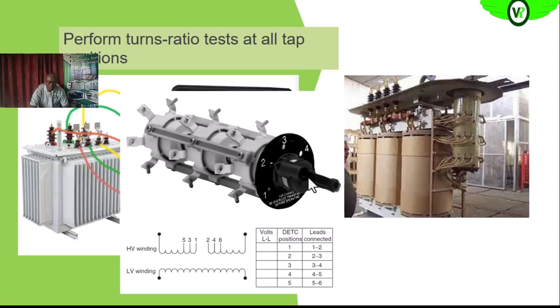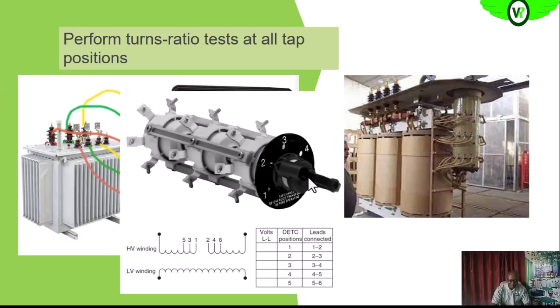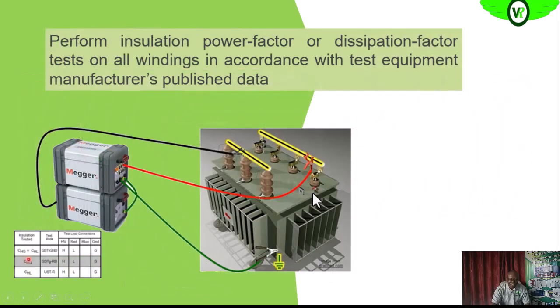So we'll do it on all tap points, or positions of the tap changer. If it is a manual tap changer, of course, that means we'll go manually and do the tap changing. Then we'll also perform the power factor or dissipation factor test. This is actually testing the insulation between both windings, the primary and the secondary winding, and then between each of the windings and the ground, between the primary and ground, secondary and ground. So that is basically what we are looking at.